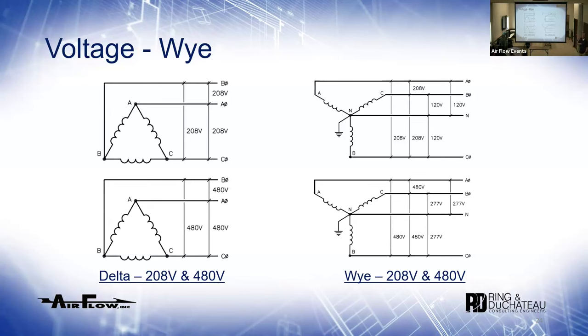When we design electrical distribution systems, my job is to get power where it's needed. If you have motors I need to get power to your motors; if you have receptacles I need 120 volts. In this case, you buy a panel board with A, B, C and a neutral. Between A and B, B and C, A and C you get 208 volts. Take the white and black wire to the receptacle and you get 120. When designing, I always want to think ahead. Back in the day they ran three-phase panels only to mechanical rooms — I've seen projects where the building has a delta panel and you can't get 120 from it.